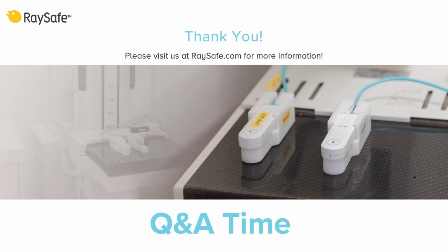But only the RaySafe calibration lab has the possibility to adjust the meter after or during the calibration. This means that if the meter is out of range, only the RaySafe calibration lab will be able to adjust it. So the users are not required to use any calibration factors or correction factors or things like that.